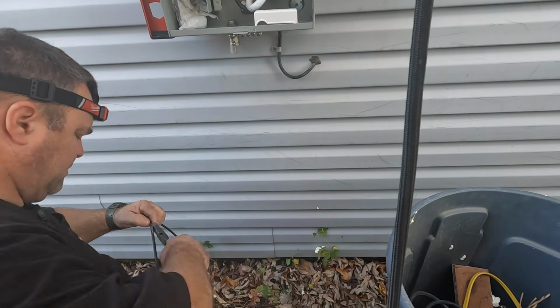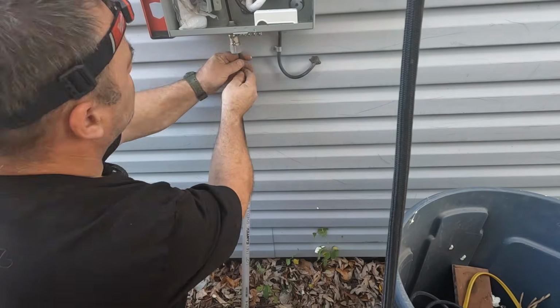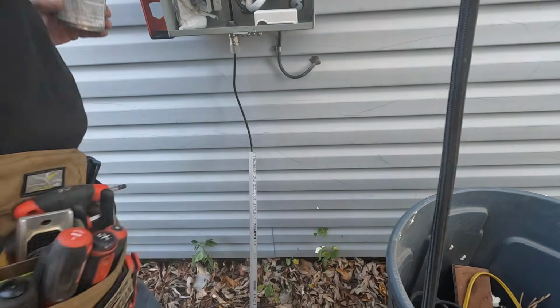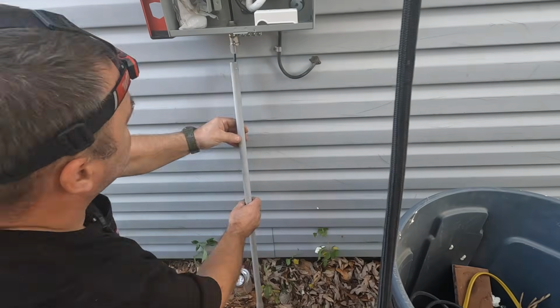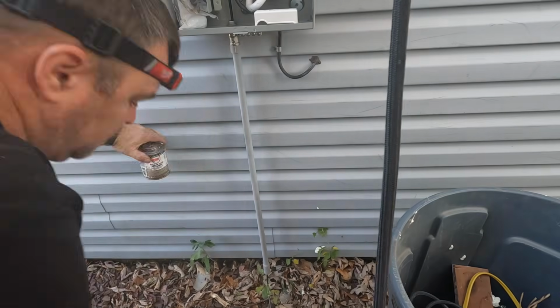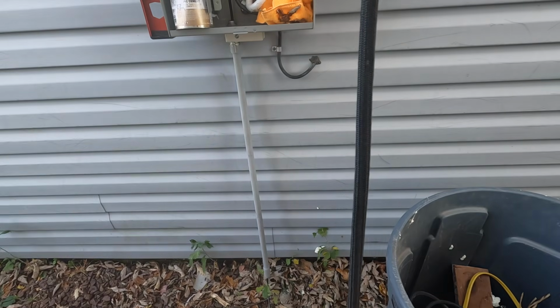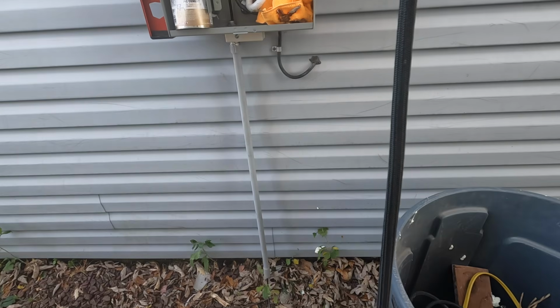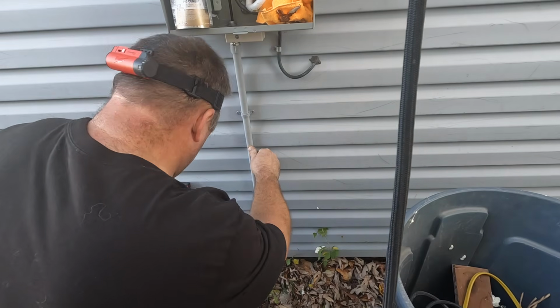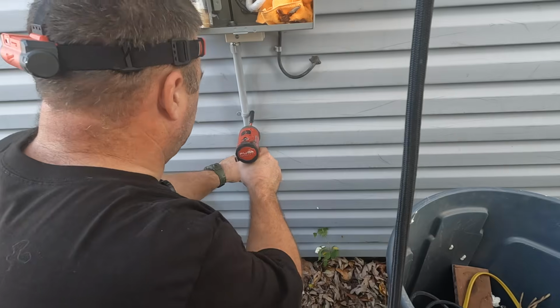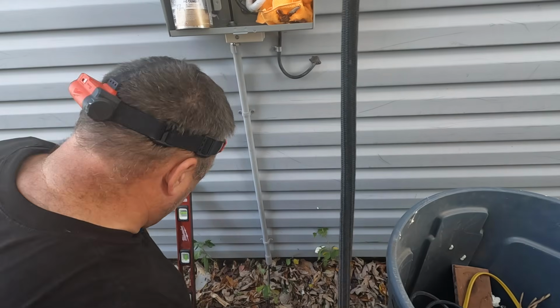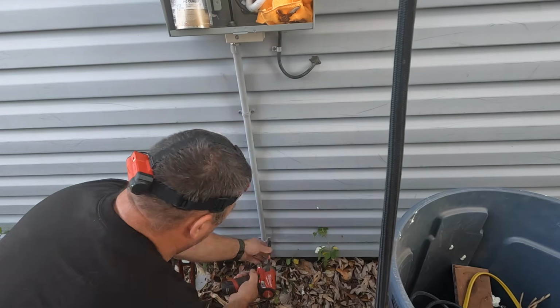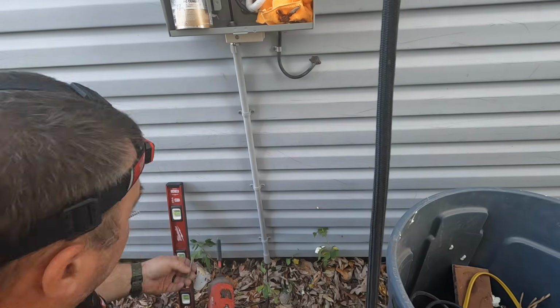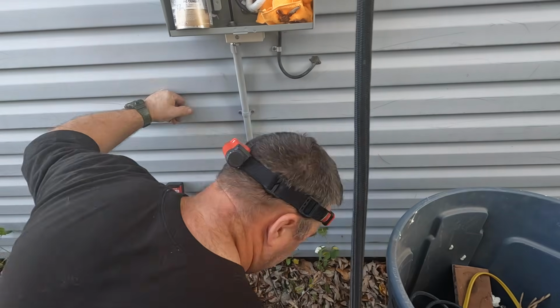And here I'm attaching, which I've never done before, a piece of PVC to protect the wire going down the wall. It doesn't technically need to be protected because it is number 6 American wire gauge. I get questions in the comments, how do I get away with number 6? Well, because my water main is what we'll call a primary electrode, and that's sized based on the size of my service entrance conductors.